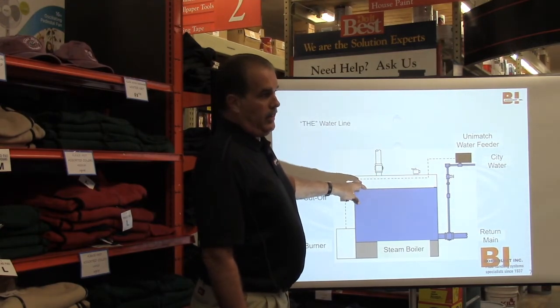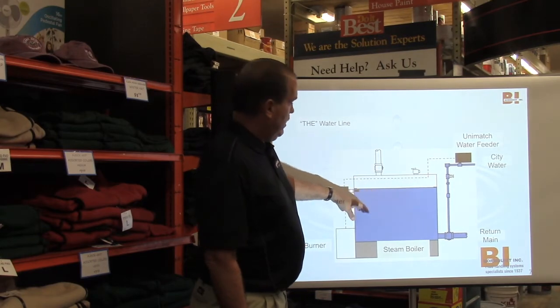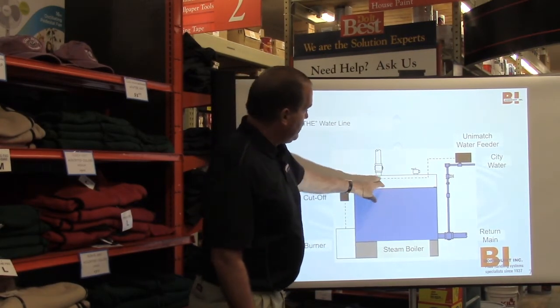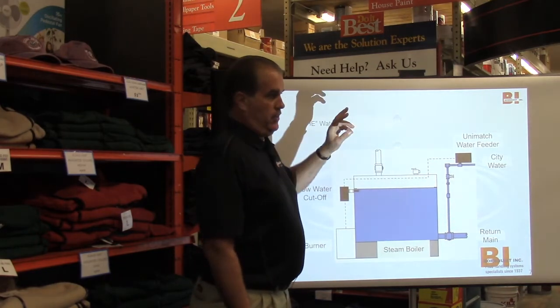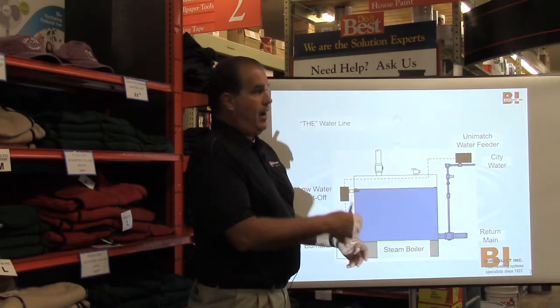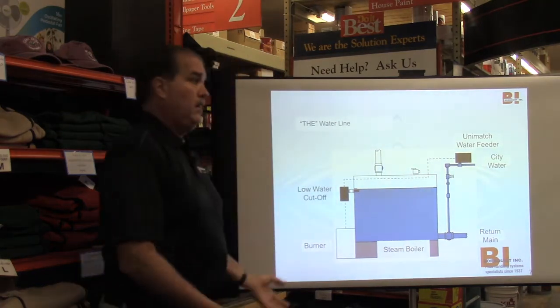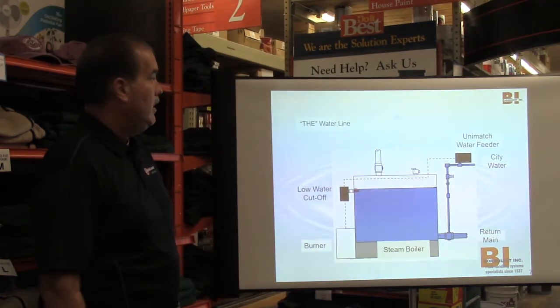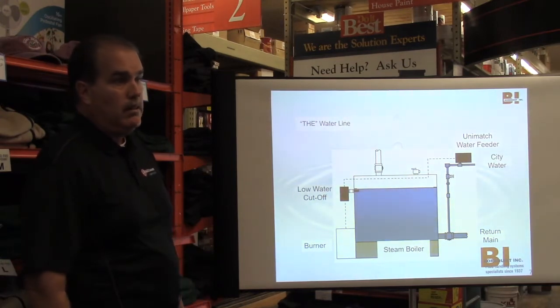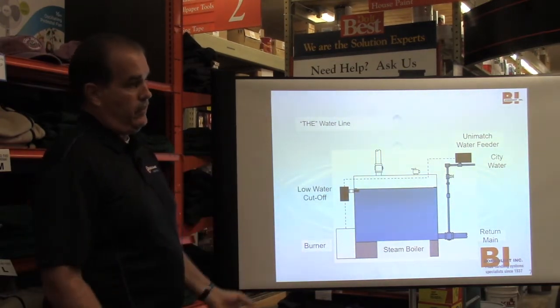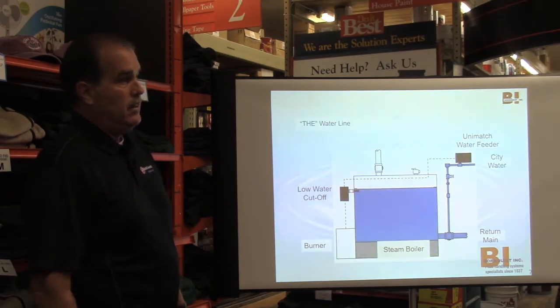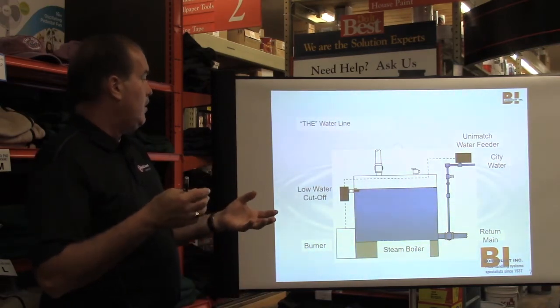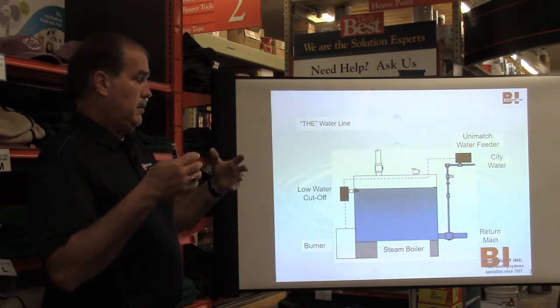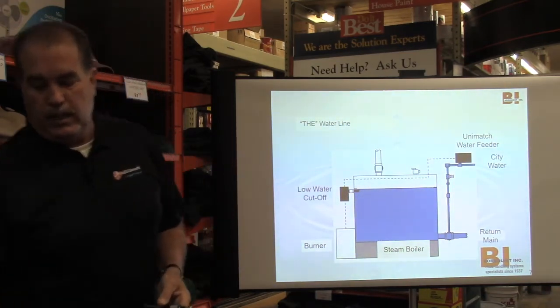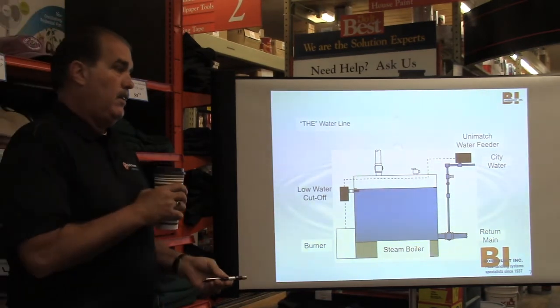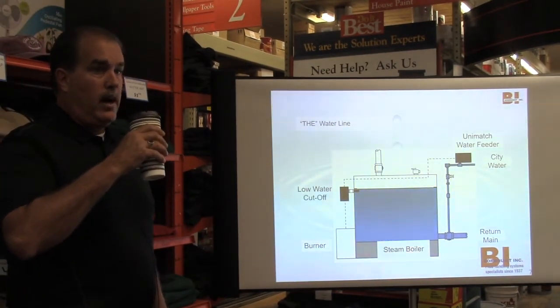A high water line is bad because you get an effect called priming. As the boiler starts firing up and boiling, you actually get water sucked up into the system rather than steam. That water now creates more condensate, and it just keeps repeating itself until you can actually start compromising the system and you won't have heat. You've got too much water and you've flooded the system, basically. So that's why those time delays are there. I will warn you though, depending on who installed them, you have to hope that they knew what they were doing, and you don't want to adjust them. Leave them where they are.